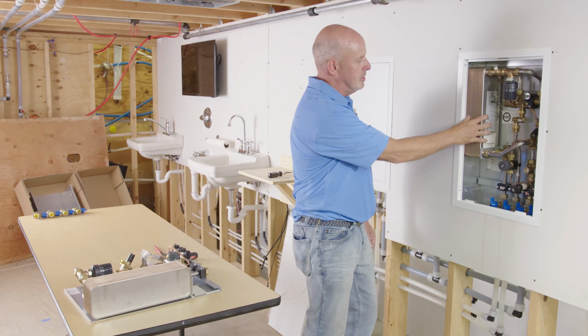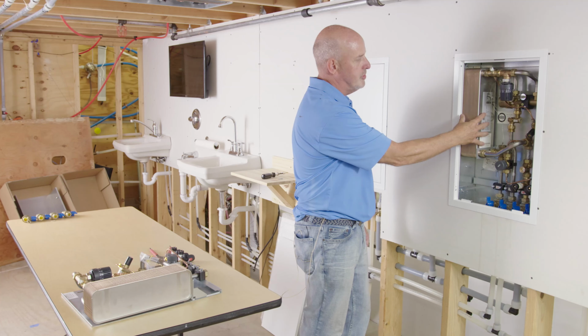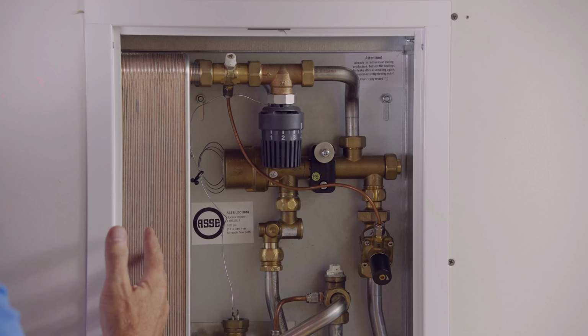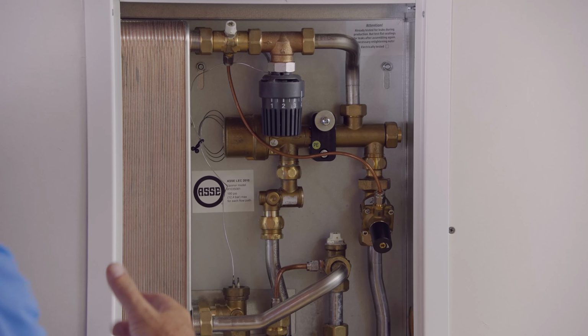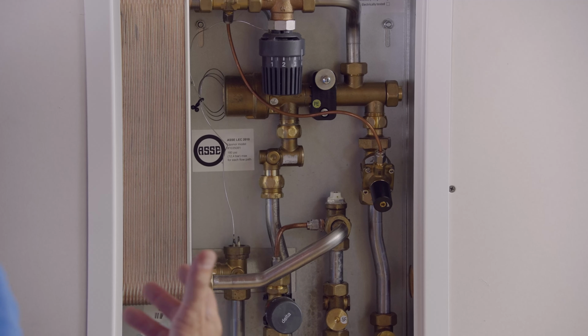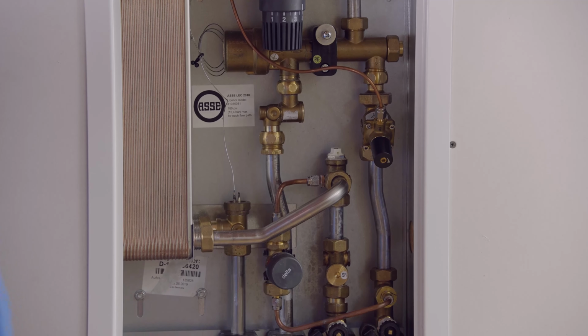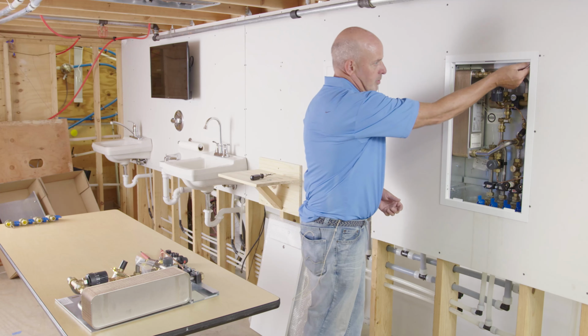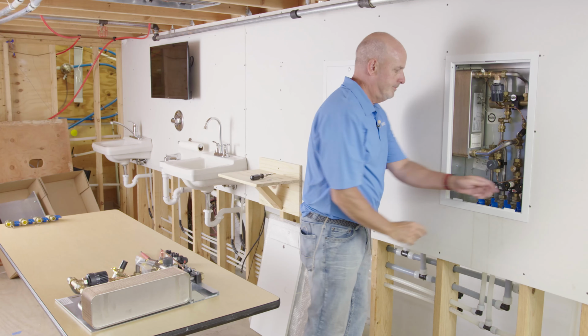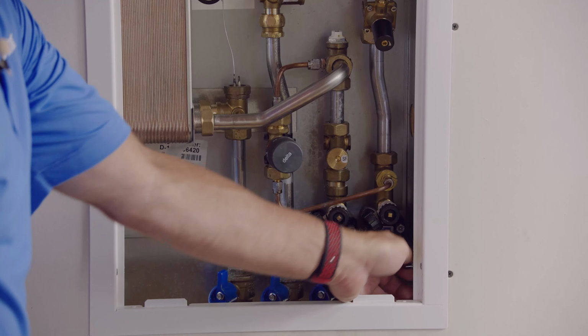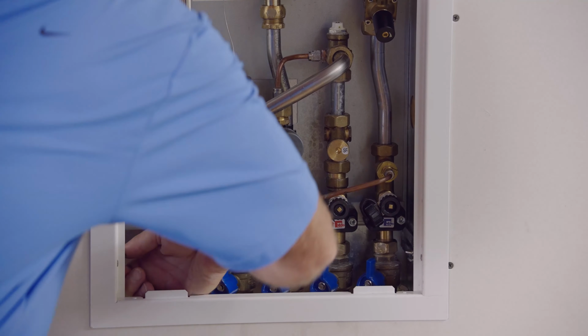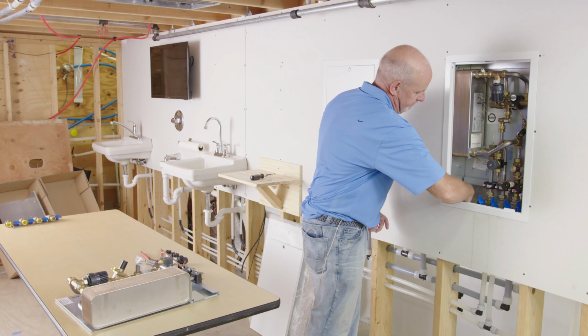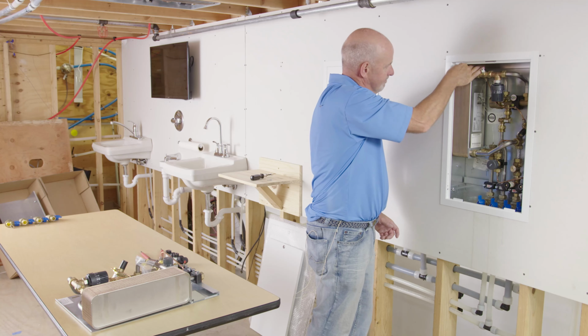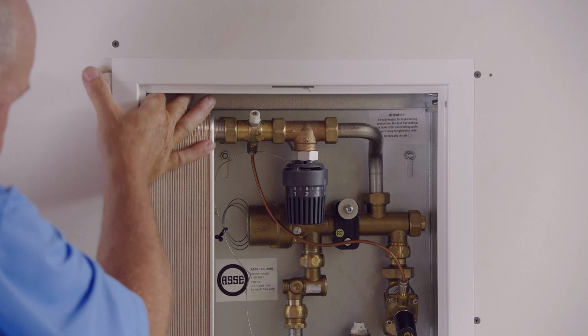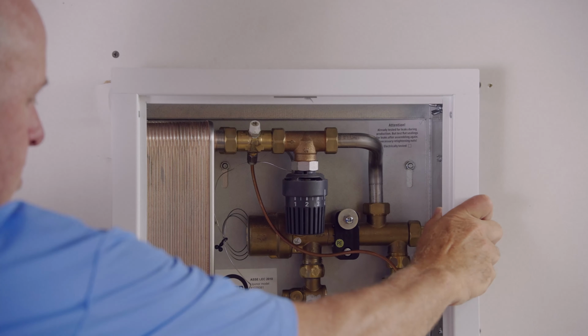Now you'll see with this unit, it's the large heat exchanger. This unit will not physically come out unless you take out the trim frame. The smaller unit, it's possible to do it, but you might want to just remove it anyways because it's easier to get at the valves. So we'll loosen up the wing nuts now and slide off the trim frame.